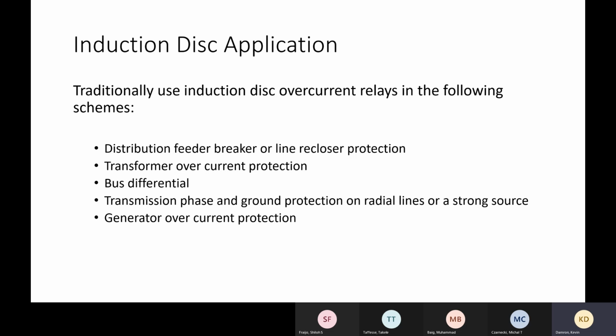So, induction-based relays, and that's what the CO class of relays are, an induction disk relay. And they're used in lots of different things. They're used from anything in distribution feeder, line reclosers, transformer overcurrent protection. They can be used for bus differentials.